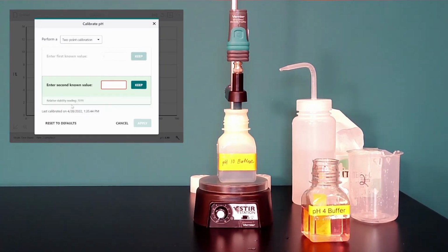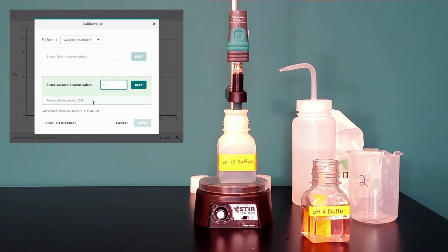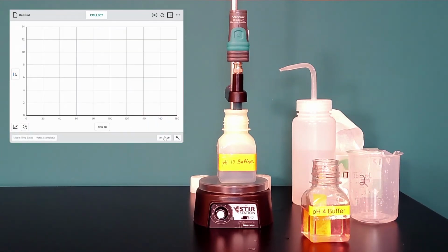Again, we look at the relative stability reading and make sure it is stable. This will take a few seconds. And then I type in the number 10, since that's the known value of the pH buffer, and press Keep. And then I click Apply. And now I want to double check that my sensor reads pH 10 in the 10 buffer, and it does.